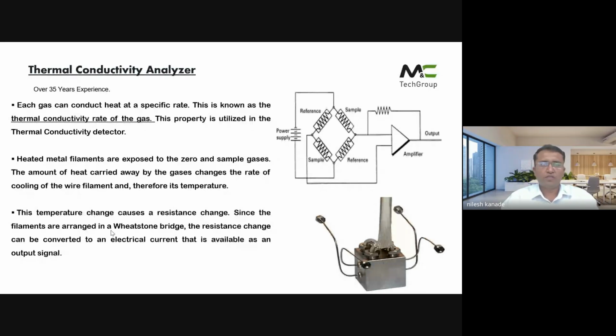The first one is the thermal conductivity analyzer. It's a sensor purely built on the gas property, because some gases have the property to carry heat, and different gases carry heat at different rates. Based on the thermal conductivity rate of the gas, the sensor is built and works on that principle. Gases with higher thermal conductivity carrying rates are the ones measured with these thermal conductivity analyzers.